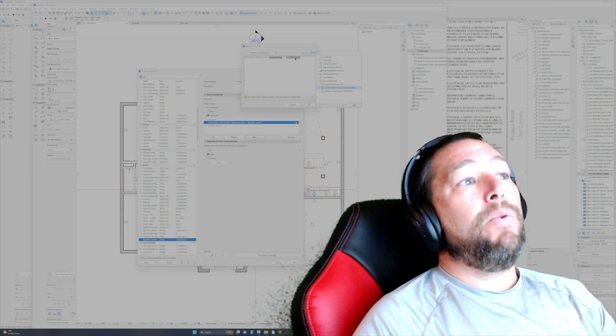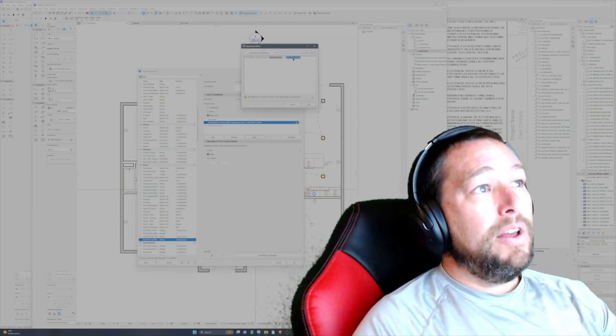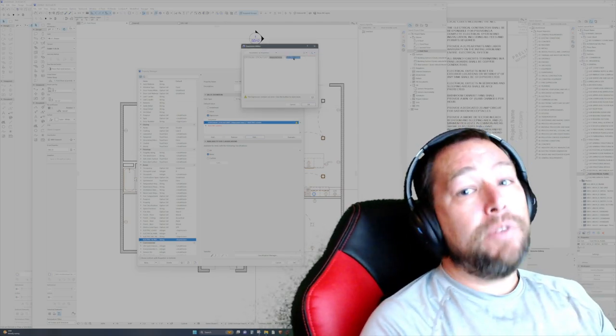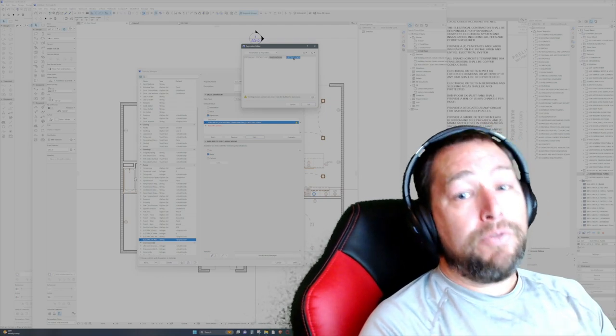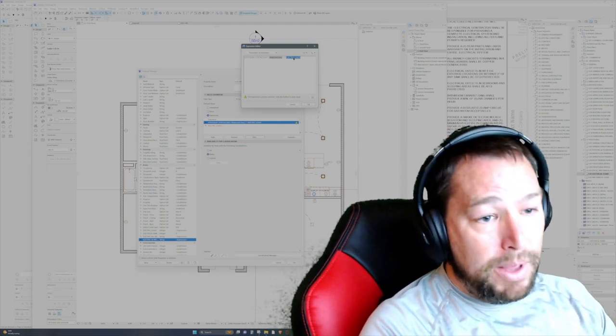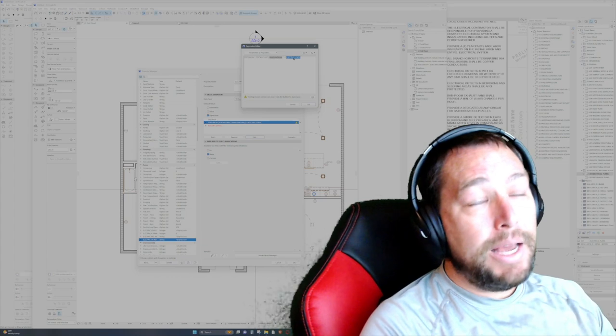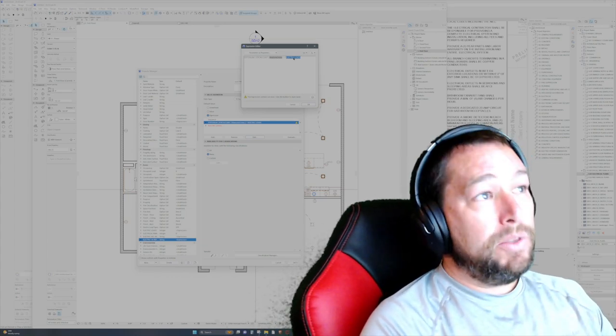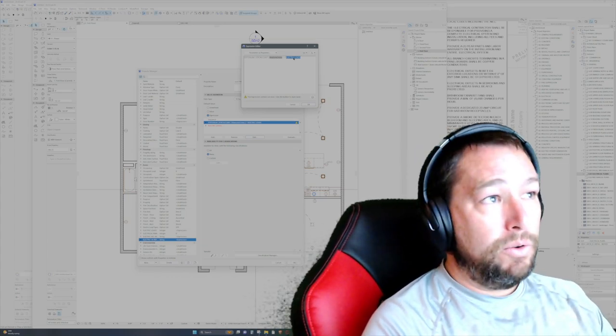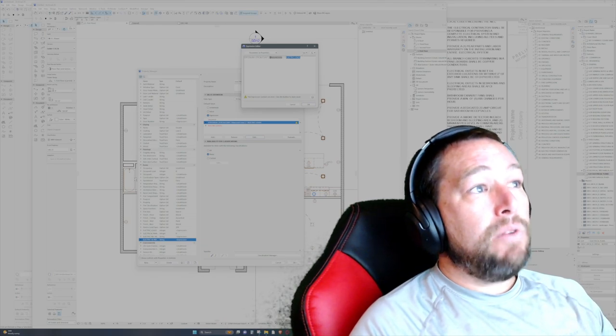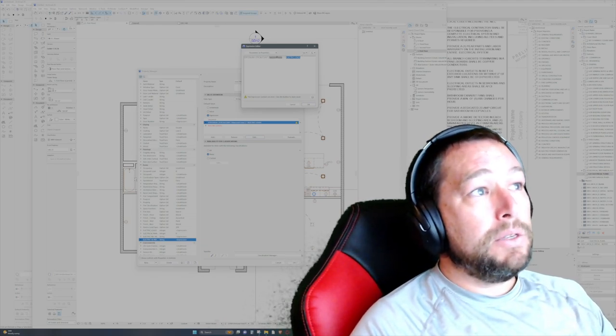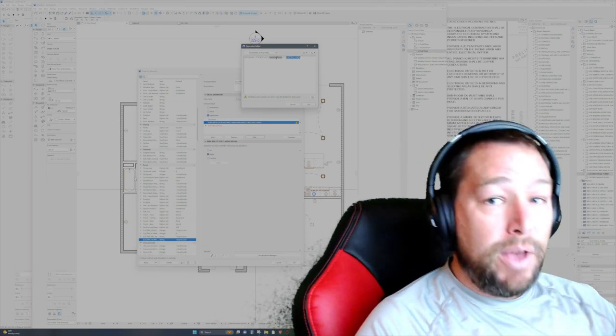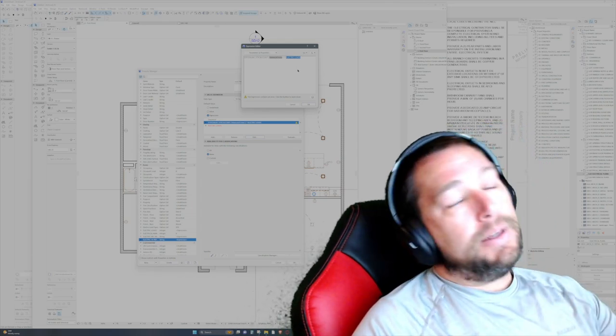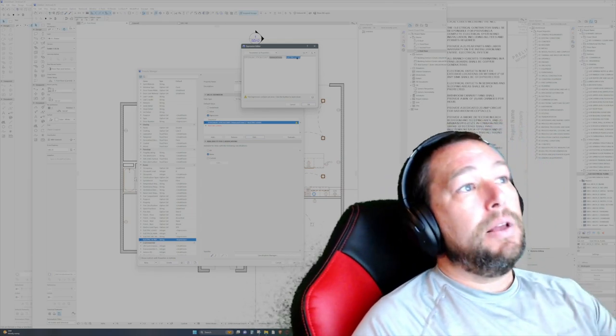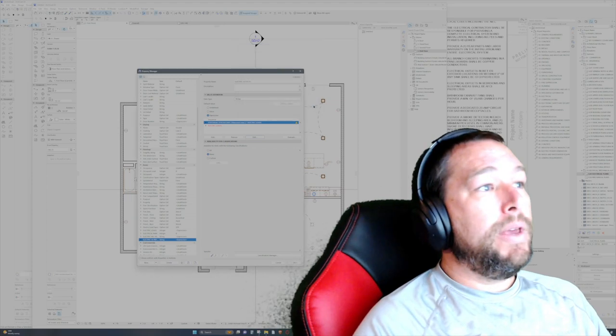Then we have the electric loads, that is the number of volt amps either from the nameplate load, or from the code value for that type of load, or from the square footage times the load. In this case, it's the square footage times the load, because what we're trying to get is if we have the 1,000 square feet times the 3 volt amps, then we get our number.